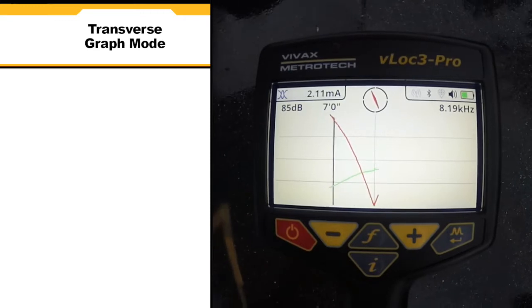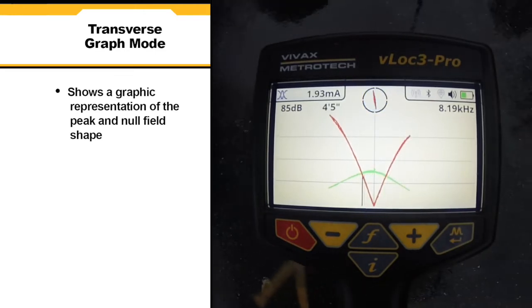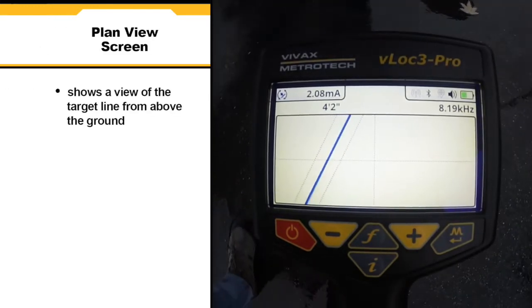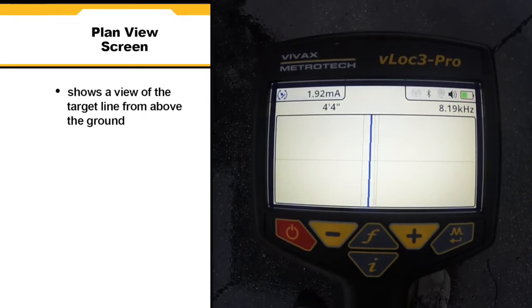In transverse graph mode we see a graphical representation of the peak and null field shape over the line. This is good for analyzing signal distortion. Plan view screen shows a picture as if you were viewing the line from above the ground. When the line is over the center of the screen you are directly over the target line.